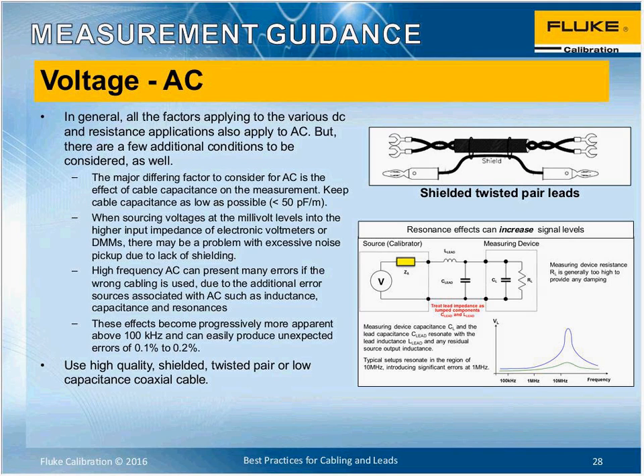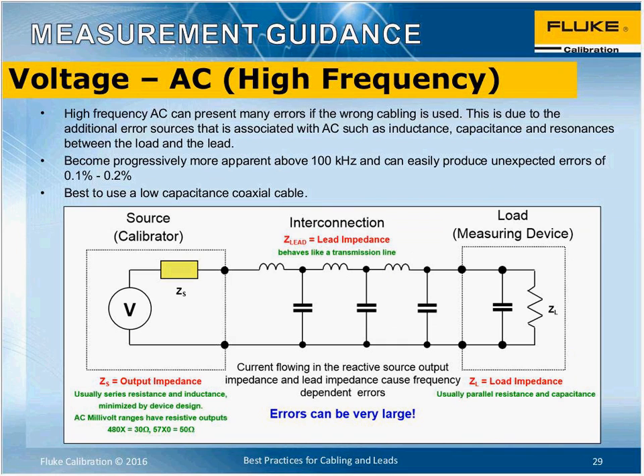AC can present many errors if the wrong cabling is used, and this is due to the error sources associated with AC, such as inductance, capacitance, and resonances. And as you go up in frequency, say above 100 kilohertz, it can easily produce more errors of 0.1 or even 0.2%. So use high quality shielded twisted pair or low capacitance coaxial cables. We mentioned a couple of things on high frequency, but this is a great diagram. Compare this to the DC diagram that we showed a few minutes ago. You can definitely see there are more error sources, just due to the physics of AC in terms of capacitance and inductance, and those need to be considered when making AC measurements and also when selecting your cables.